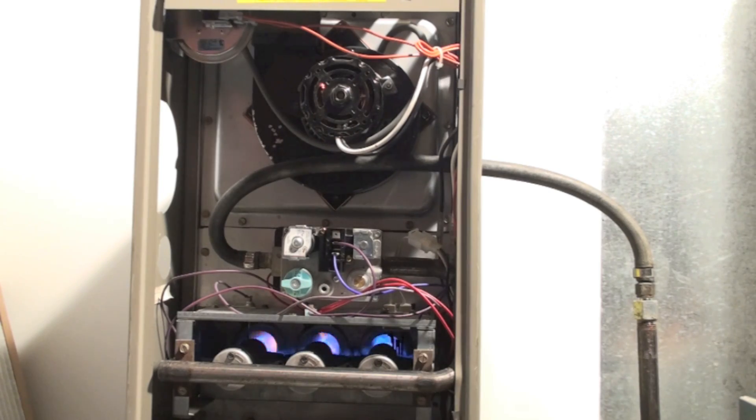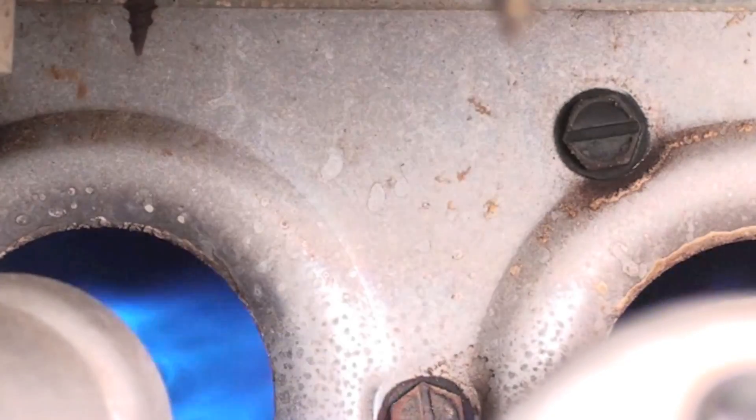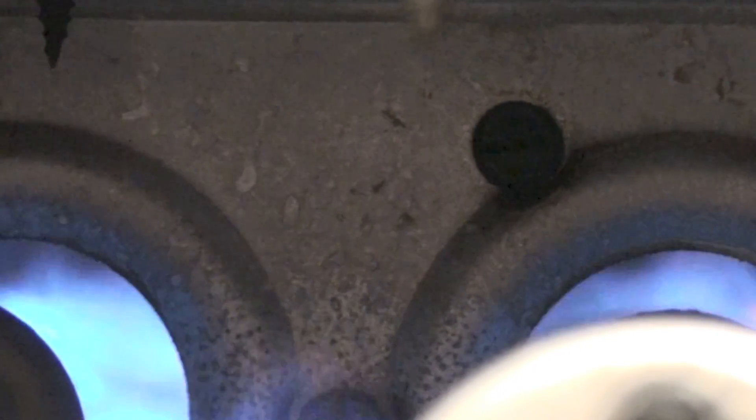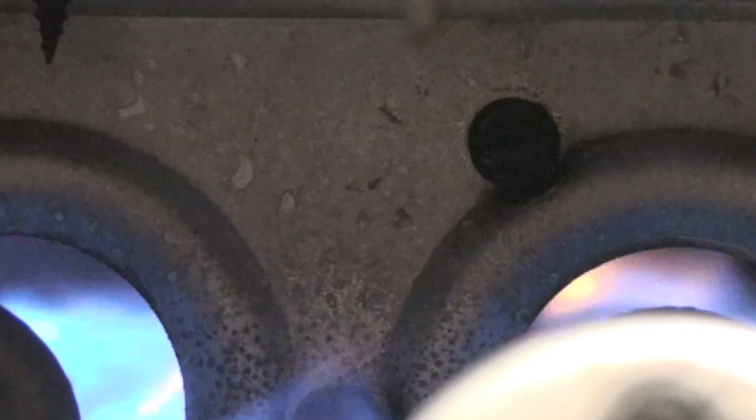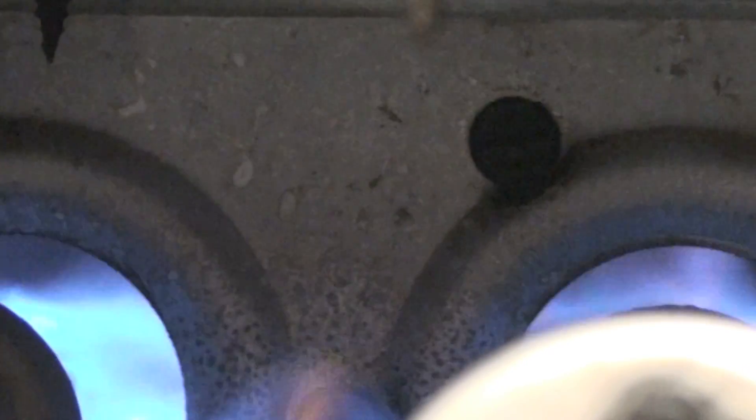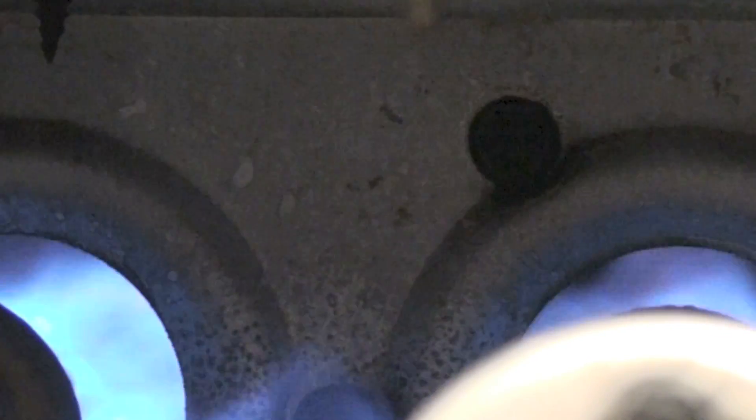And now you're looking for changes in the burner. With your burners on, you're going to be looking for when the fan starts. You want to be sure there's no change in that burner. The burner flame stays just the same.